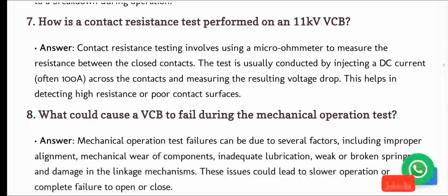7. How is a contact resistance test performed on an 11 kV VCB? Answer. Contact resistance testing involves using a micro-ohmmeter to measure the resistance between the closed contacts. The test is usually conducted by injecting a DC current, often 100 A, across the contacts and measuring the resulting voltage drop. This helps in detecting high resistance or poor contact surfaces.